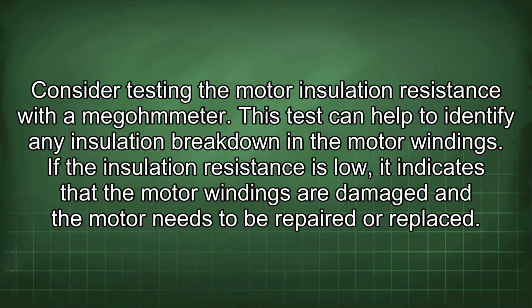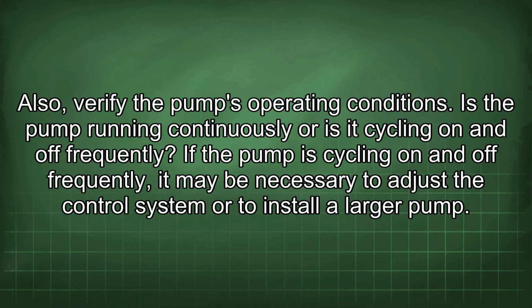Consider testing the motor insulation resistance with a megohmmeter. This test can help to identify any insulation breakdown in the motor windings. If the insulation resistance is low, it indicates that the motor windings are damaged and the motor needs to be repaired or replaced. Also, verify the pump's operating conditions. Is the pump running continuously or is it cycling on and off frequently?